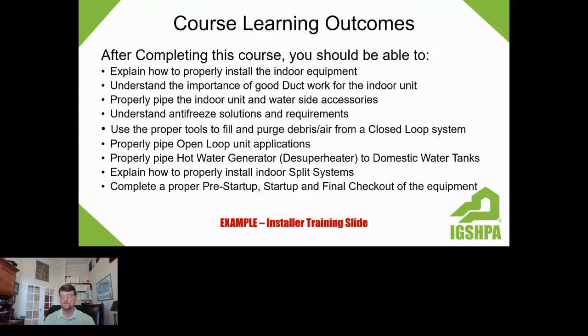So it's a water-based unit, so obviously there's some water fluid piping that's going to be required, so we'll cover all of that. If there's an antifreeze system going to be used on a closed loop system, we'll talk about antifreeze and the requirements for that. Also, we cover the proper tools that are required to do a geothermal installation to fill and purge the fluid system for the closed loop. So if you're doing a closed loop system, we'll cover those tools as well as even the open loop system.